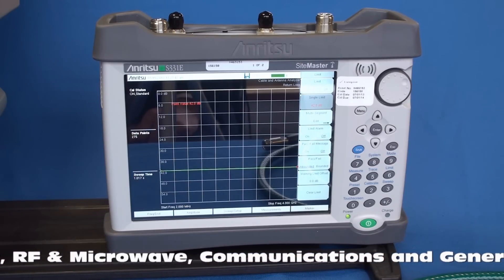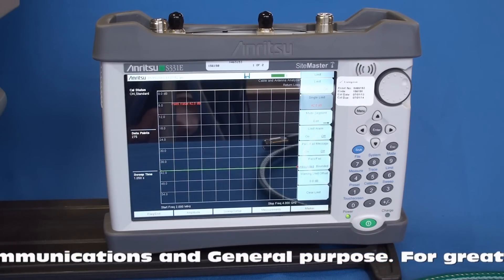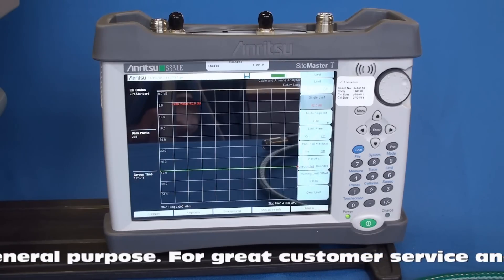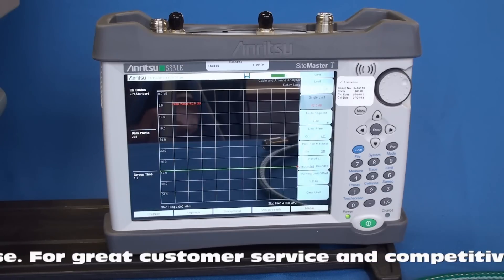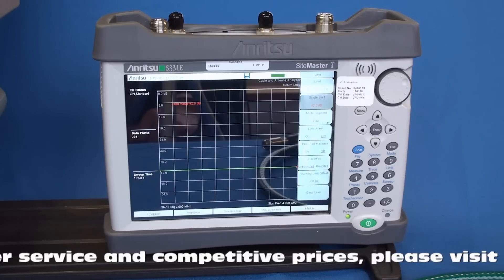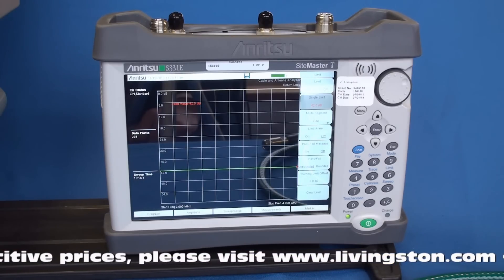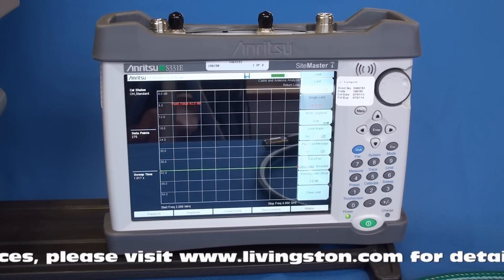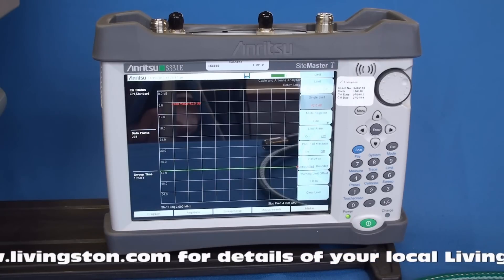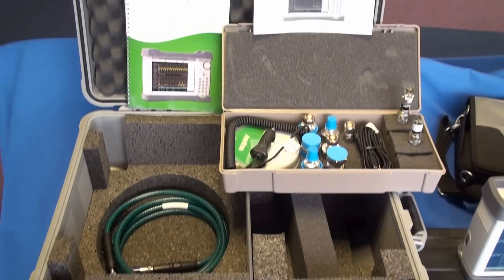So let's get started. Before you take a series of measurements you should take care to calibrate the Site Master to a set known baseline against which you will make your measurements. To do this you will need a Site Master that has been switched on at least five minutes and the battery fully charged before the procedure, to allow it to warm up and eliminate temperature variations in the measurements. The calibration is going to take place at the end of a phase stable cable which will normally be used to attach the Site Master to the equipment needing testing. This will ensure that the cable parameters are then negated out of any measurements.